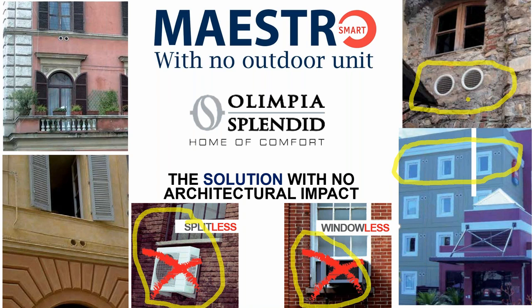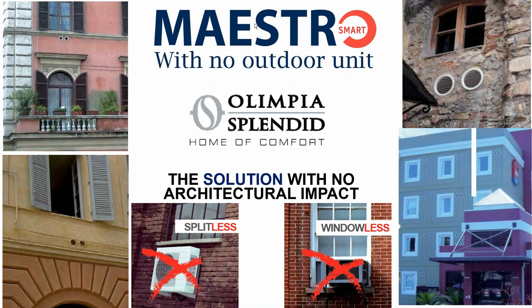So here is how you can install this equipment. It has to be an outside wall. The wall can't be any longer than 39 inches in depth, nor can you add any elbows or bends to the duct. So it has to be a straight shot from the inside wall to the outside wall, or inside of a wall to the outside of an outside wall. So, you know, that being said, let's move on.